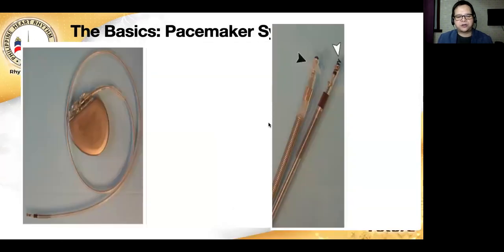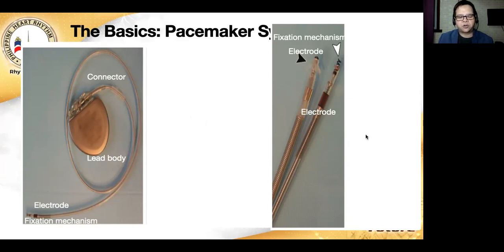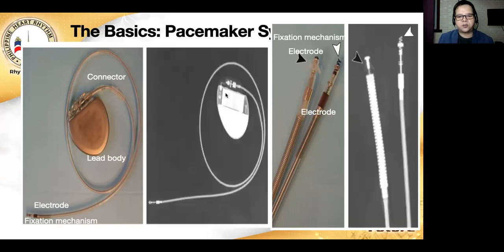So the basic pacemaker system consists of the pulse generator. Okay, then the lead with the different parts: the fixation mechanism at the tip, the pacing and sensing electrodes, the lead body, and the connector, which attaches to the pulse generator. And these are the tips of the leads with either a passive or active, screw-in fixation mechanism, then your electrodes. And so correlating with the X-ray views, we can see the images here. Okay, and sometimes you need a close-up view to get a clearer image of the lead as well as the device.